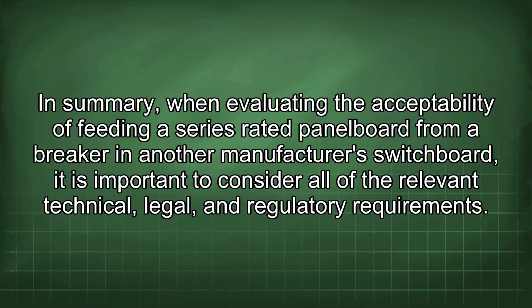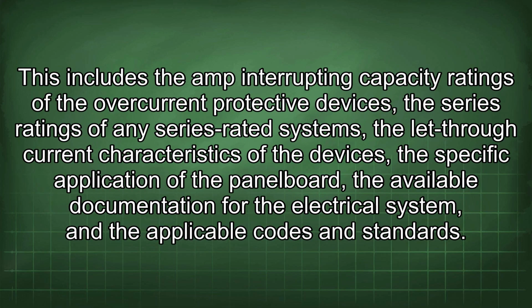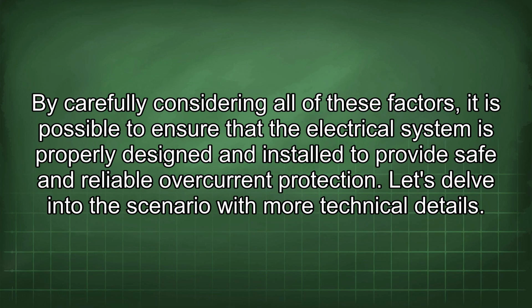In summary, when evaluating the acceptability of feeding a series-rated panelboard from a breaker in another manufacturer's switchboard, it is important to consider all of the relevant technical, legal, and regulatory requirements. This includes the amp interrupting capacity ratings of the overcurrent protective devices, the series ratings of any series-rated systems, the let-through current characteristics of the devices, the specific application of the panelboard, the available documentation for the electrical system, and the applicable codes and standards. By carefully considering all of these factors, it is possible to ensure that the electrical system is properly designed and installed to provide safe and reliable overcurrent protection.